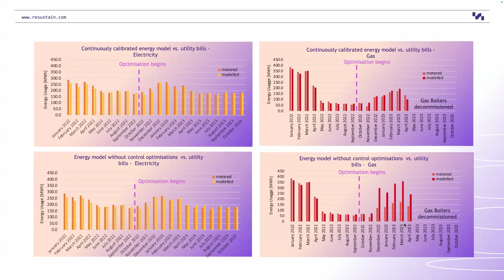So you can see here for the electricity, not much. We weren't really hitting the electricity. What we were hitting was the gas usage. As you see, we dropped the fresh air down and we dropped the temperature of those reheat coils down. And as you can see, the gas usage decreased significantly once we went into optimization over those winter months.